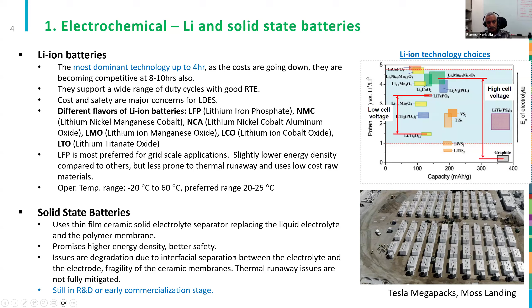But thermal runaway risk is not completely eliminated because the lithium cathode is an oxide material - you already have oxygen in there. So even without oxygen from outside, that can ignite the battery. Once it ignites, it can go into thermal runaway. But because you don't have a lot of organic materials, it's not as bad compared to the other ones.